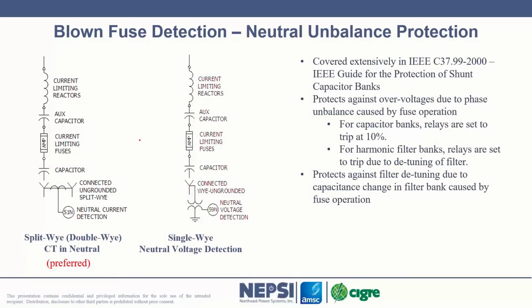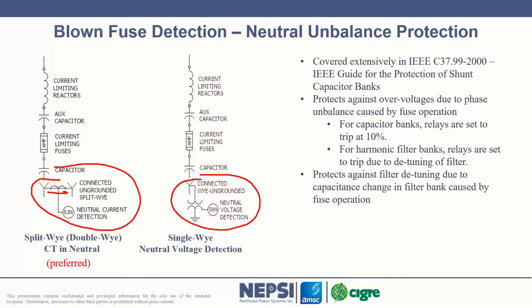Blown fuse detection: just realize that whenever there's a capacitor bank within a harmonic filter bank, we're doing some type of blown fuse detection. Either it's going to be a split Y, where we put a CT in the neutral of two Y-connected capacitor banks to detect a harmonic current flowing through here because of an impedance imbalance in your filter, because we've had a fuse operate. And that could be an internal fuse or an external fuse.